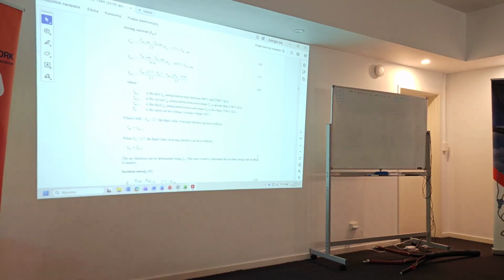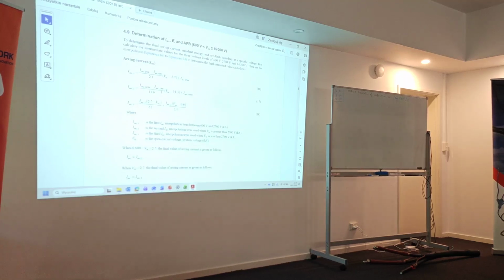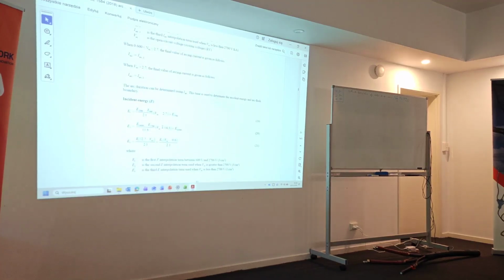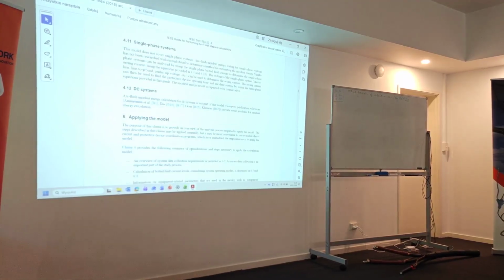Give me a second. Here. So here is the interpolation part. You have one arc current, a second arc current that you calculated, and then you recalculated the one in between, here. And the same is with the energy. So it's always the interpolation between 2 points. You don't specifically calculate for 6 kV, you calculate for 2.7, for 14.3, and then you recalculate the point in between. That's how the calculation works for the IEEE 1584.